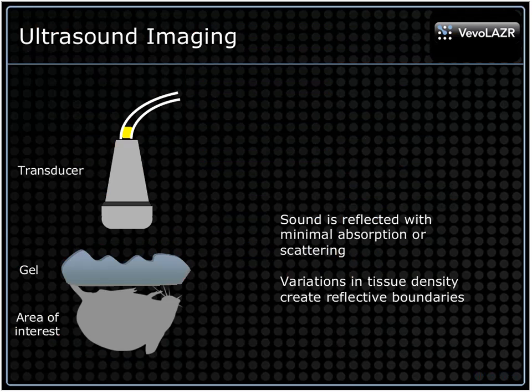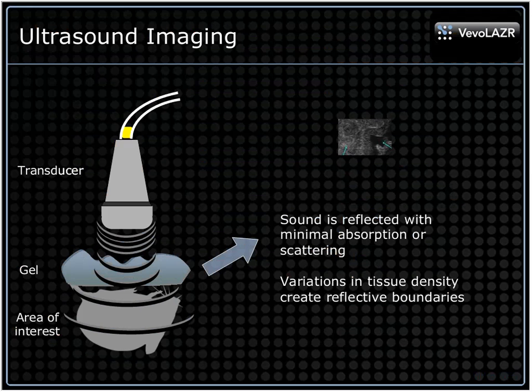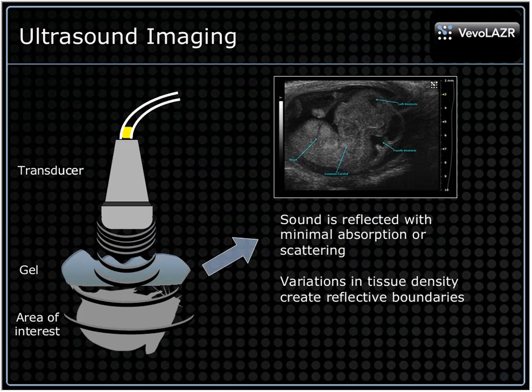Now, with micro-ultrasound, I'll just briefly describe how it works, and then I'll describe some of its advantages. We've got an ultrasound transducer, which transmits a sound wave through a coupling medium like gel. It goes into the target of interest, and the sound is reflected, and we can build an image out of that reflected and then detected sound. This image that you're seeing here is a mouse embryo, and essentially anything that's bright in this image is reflecting the sound strongly.